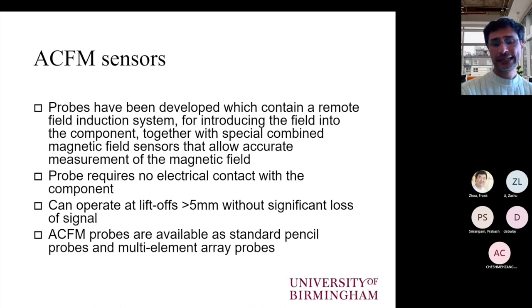inspection quality overall. The ACFM does not require electrical contact in the same way that eddy current testing and magnetic flux leakage do not require electrical contact. And they can also operate at higher liftoff than eddy current testing. So typically, liftoffs up to 5 millimeters are possible, especially if we are trying to detect larger defects. If it's smaller defects, of course, we need to try to be as close as possible. Eddy current testing, however, above 2 millimeters, the signal becomes very low. So it is not a very good idea to try and increase the liftoff beyond that. And ideally, you should keep it even below 1 millimeter if feasible.